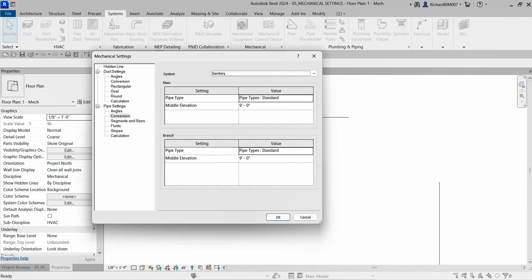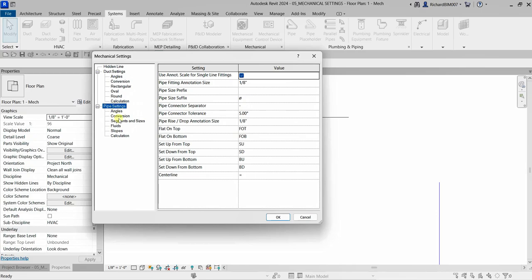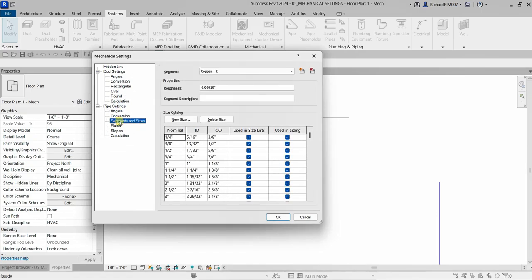Another setting to explore is Pipe Segments and Sizes. These settings control the material and sizes for a pipe type. When 'Used in Size List' is selected for a size, that size will be available when using the pipe tool. When 'Used in Sizing' is selected, that size will be used when the duct or pipe sizing tool is applied.